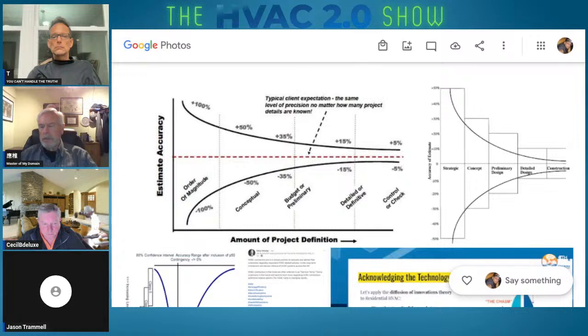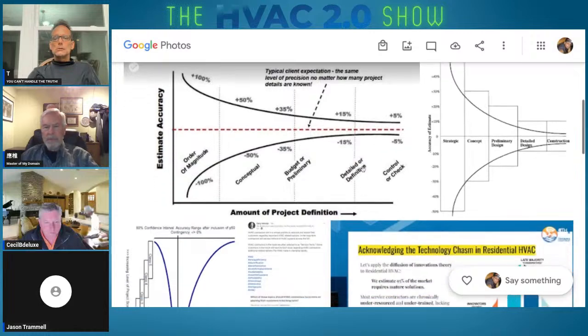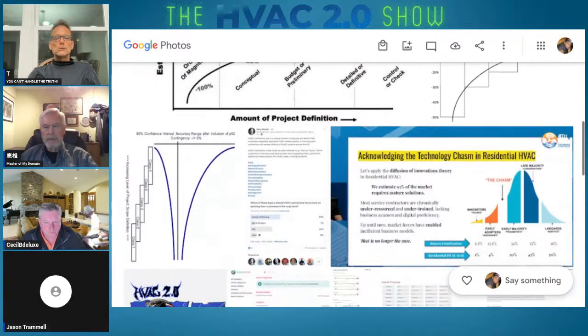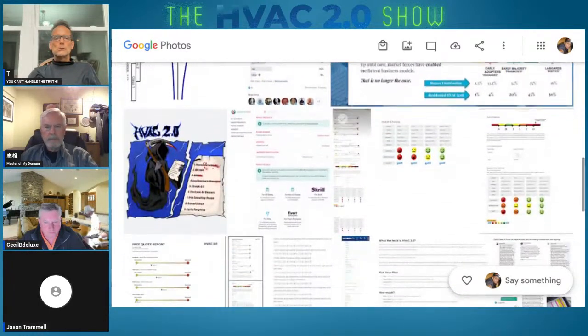But that's not the fault of the equipment. The Manual J is accurate in that respect; it's the delivery system that's messed up. Most contractors, if they do a Manual J, will add another 6,000 BTUs per ton just to be safe, even though the fudge factors are already built in. So you're oversizing it by 50% on top of 50%.